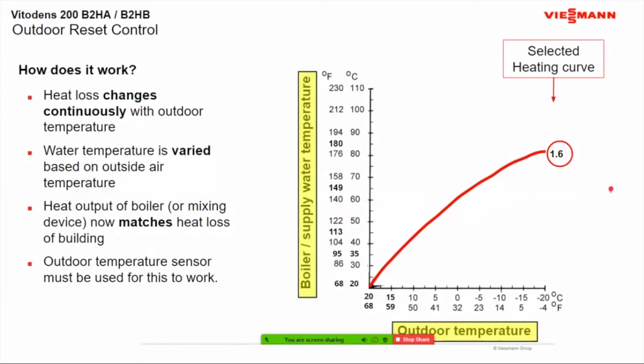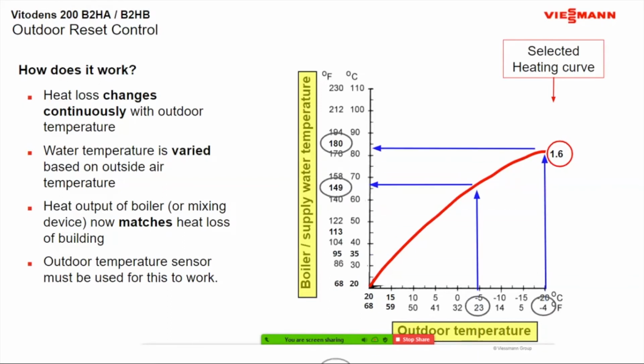So it's pretty cool. Just for an example here, I put up a heating curve of 1.6. That's usually where you're going to be if you want higher temperatures, like 180. So now you can see 1.6 is going to bring you closer to that 180. I took the lines out so you can see, without the lines in the way, the same outdoor temperatures that we had before, now with just a different slope. Now you can see on that -4 day, we're going to go to the maximum of the boiler.